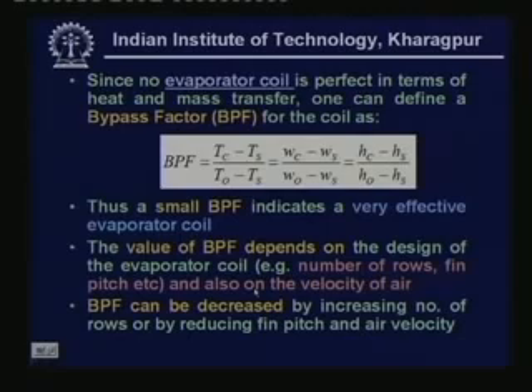Since no evaporator coil is perfect in terms of heat and mass transfer, one can define a bypass factor BPF for the coil. The bypass factor BPF is equal to Tc minus Ts divided by T naught minus Ts, which is also equal to Wc minus Ws divided by W naught minus Ws, that is equal to Hc minus Hs divided by H naught minus Hs. Here C is the actual exit state and S is the exit state corresponding to the coil ADP. So that is shown on this figure.